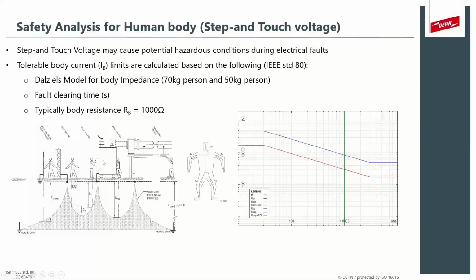The same is true if someone stands and touches an energized part which is bonded to the electrical earth, and there's a fault, and this metallic part gets energized, and it also enters the ground. If a person stands on a specific point on that voltage curve and touches the metallic part, which is at a different potential, that will cause current to flow from the hand to the feet. And that can also cause ventricular fibrillation and electric shock. If you look at our little stick man, this is referenced from an IEC standard, also for human step and touch limits. You see that the current will flow from the hand down to the feet. And that also causes touch potential and electric shock.